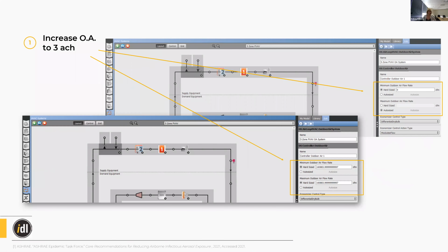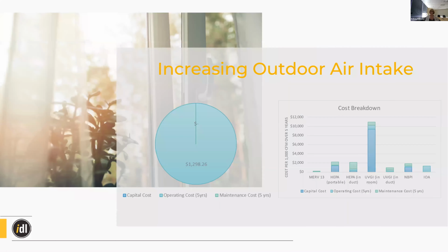And so modeling that was relatively easy. We just opened up the dampers and upped our outdoor air intake to 3 air changes per hour. And that was almost no capital cost, well, 0 capital cost, because you don't have to do anything different. We can all just tell our HVAC system to take in more air. So it's all operating costs.